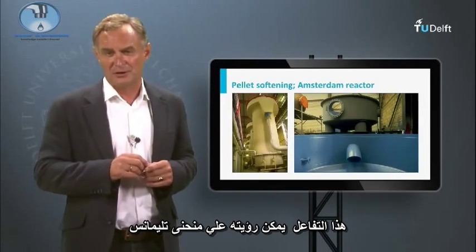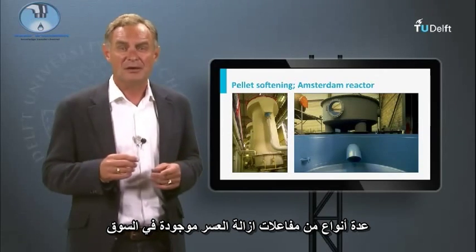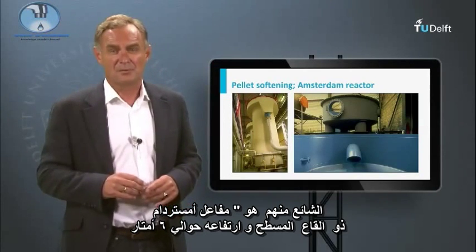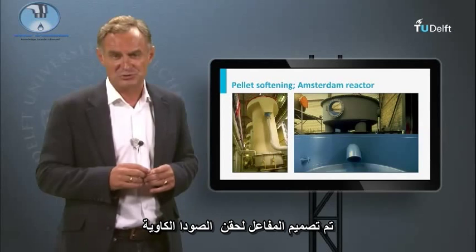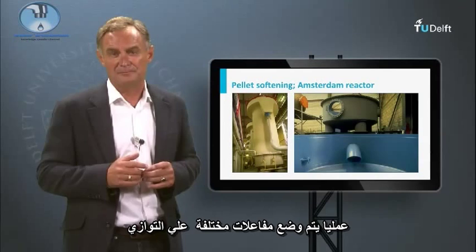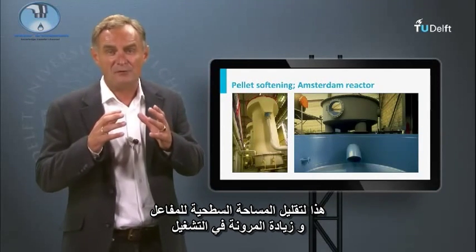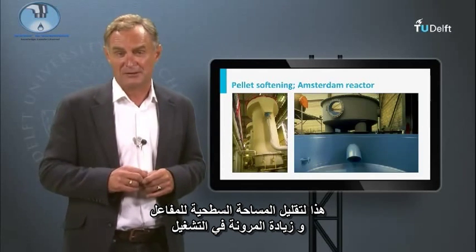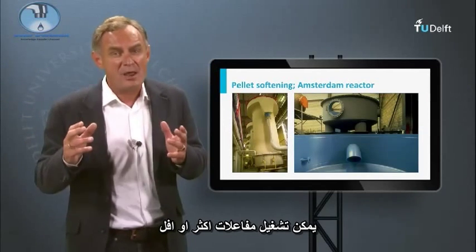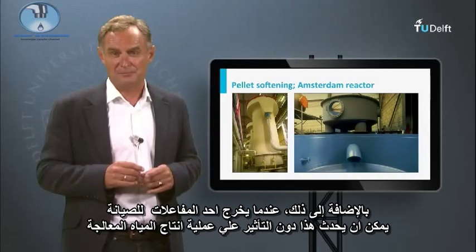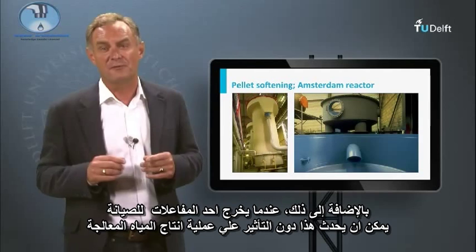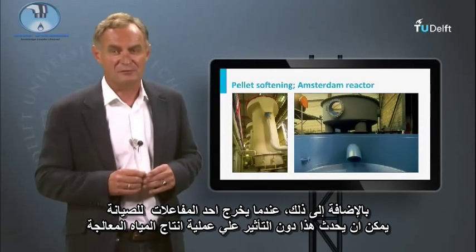Several types of softening reactors are on the market. A common one is the Amsterdam reactor, which has a flat bottom and is about six meters high. The reactor is designed for the dosing of caustic soda. In practice, different reactors are placed in parallel to reduce the surface area of individual reactors and to promote flexibility in operation. When flow varies due to seasonal fluctuations, more or less reactors can be put in operation, and when maintenance of one reactor is needed, it can be taken out of operation without affecting production.